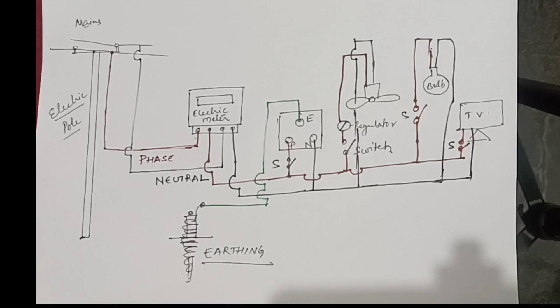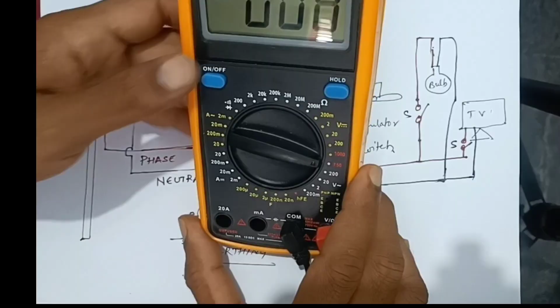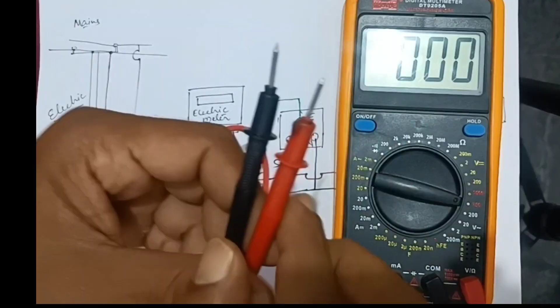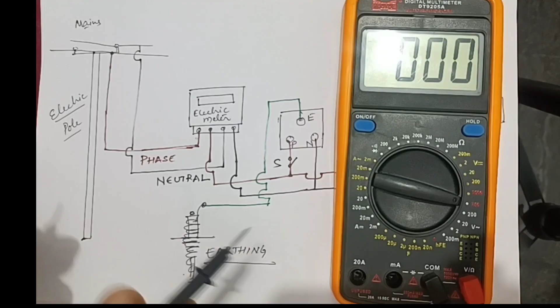To check the connections, whether it has been properly done or not, we have to use the multimeter and set it to 750 volt AC, switch it on, and the electric probe has to be connected, for example like this. These two probes have to be connected to the meter, such as this phase point and neutral point - this is phase and this is neutral - and check whether the voltage of 230 to 240 volt is coming or not.